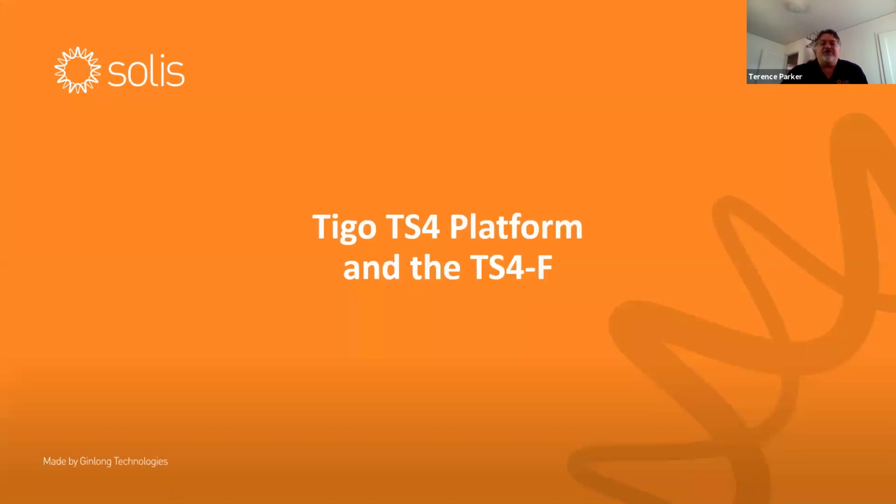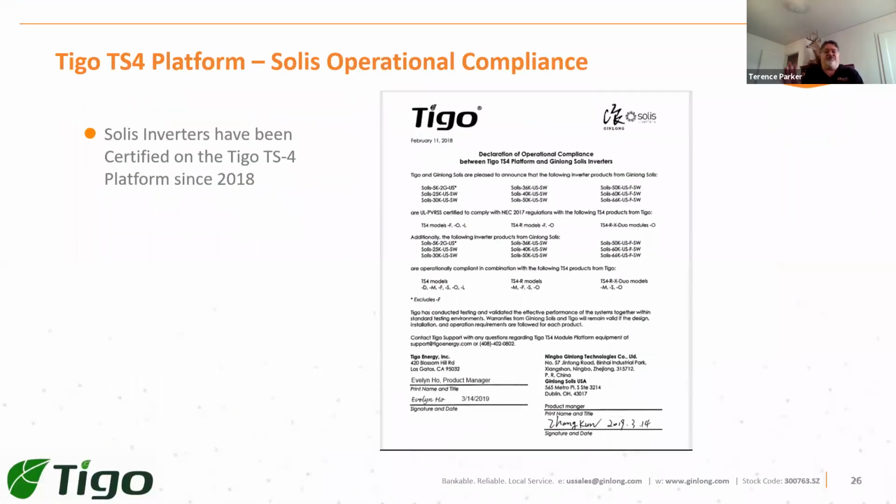So, Gary, I want to bring you back in to talk a little more in detail about the Tigo platform and these TS4-F units. Gary? Yeah, absolutely. So first of all, about compliance and compatibility. We UL list all of our products with the inverters, and that means that we test with UL and with Ginlong. The three of us get together and we do testing, and then we UL list it and put out these letters of compliance. So it's very important to always check that your equipment has all been tested together.